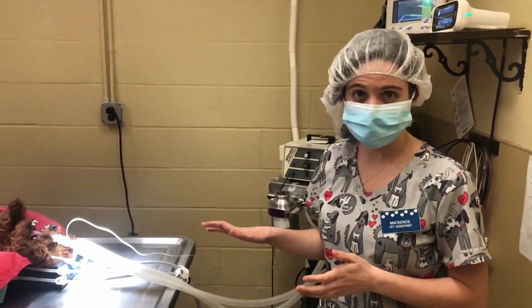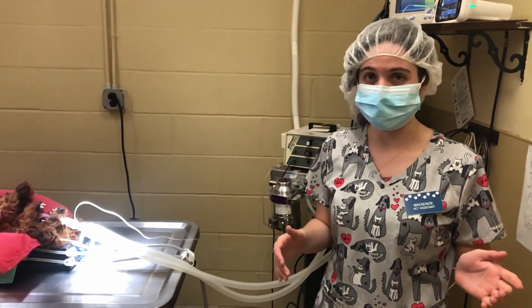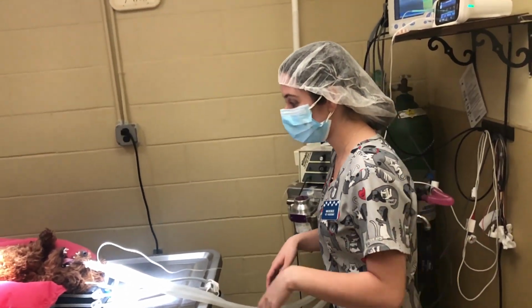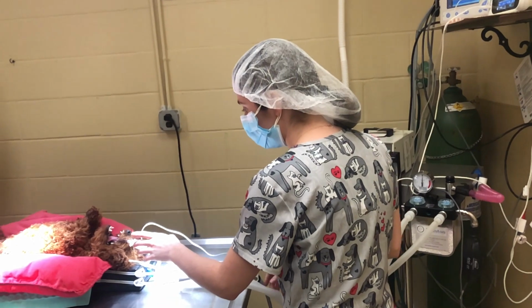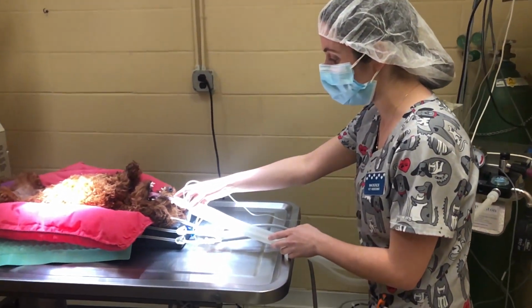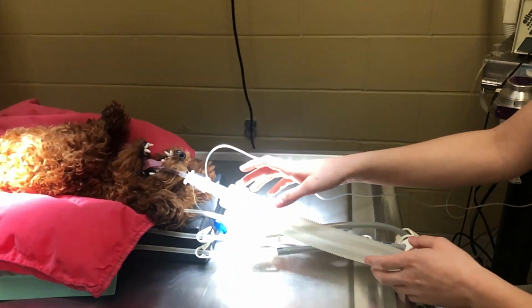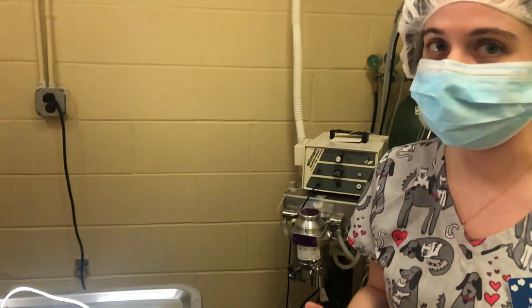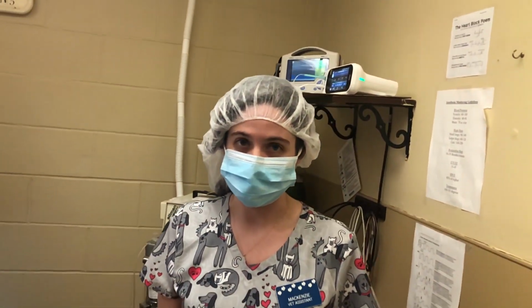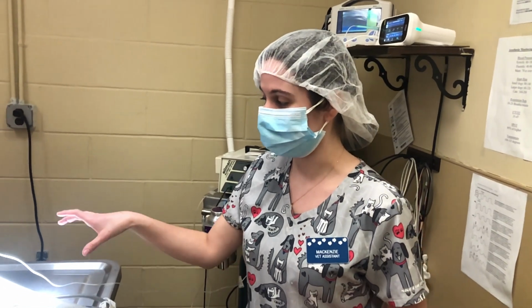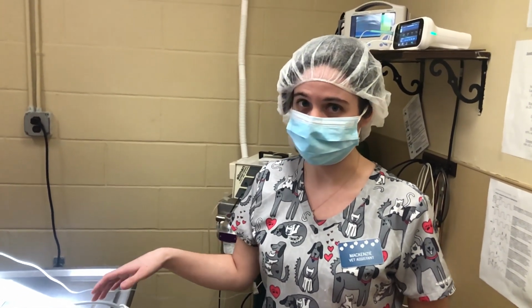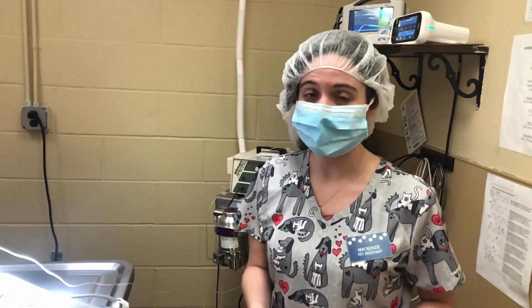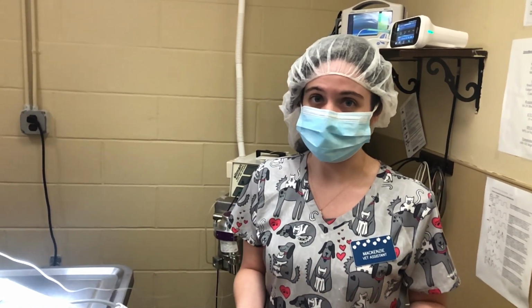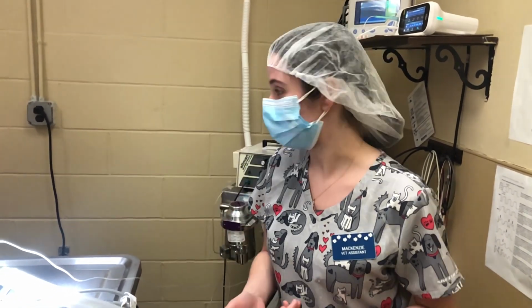So now that our patient is in surgery, we can start with one of the monitoring equipment. I've already placed the capnograph, attached it to the ET tube of the patient and the breathing circuit, and what that does is it measures the amount of CO2 that the patient is breathing in and out, and also the amount of CO2 in the ET tube and the breathing circuit, which is ETCO2, and it also measures the patient's respiratory rate in breaths per minute.